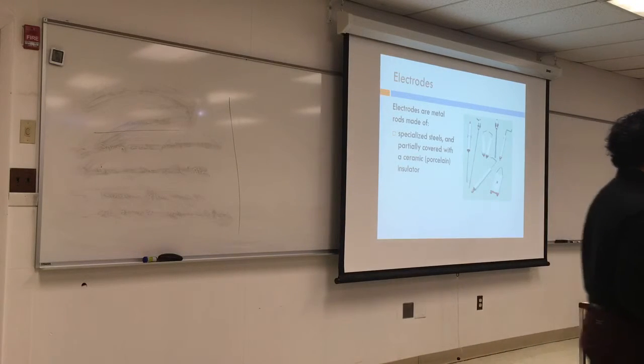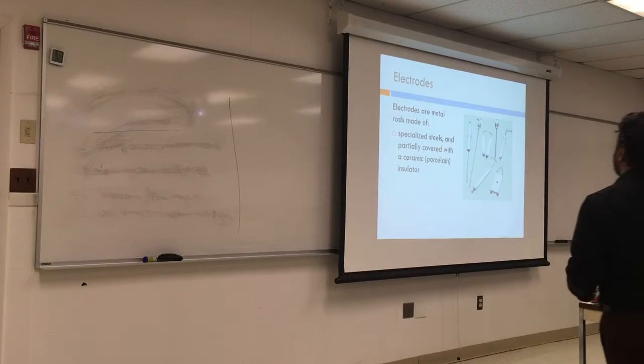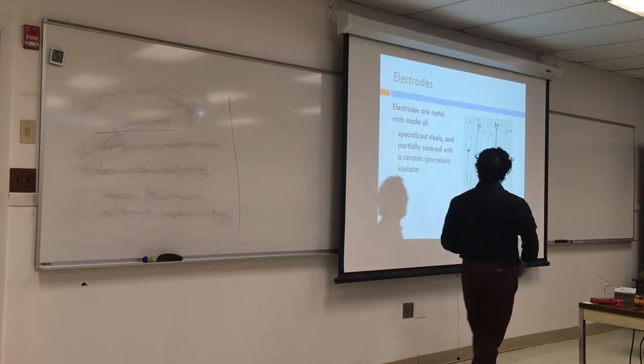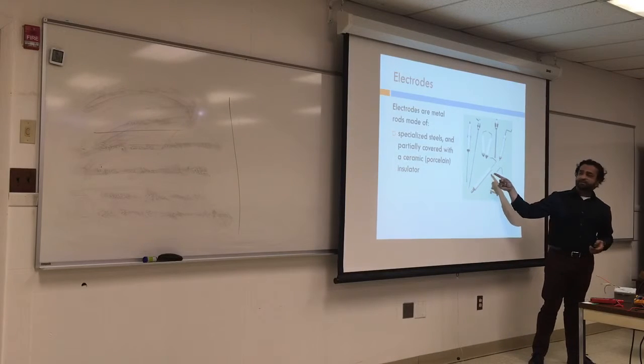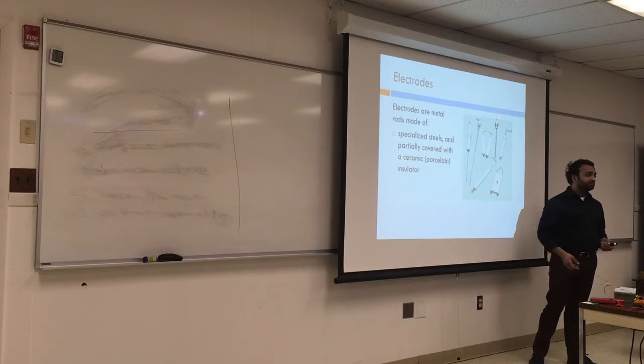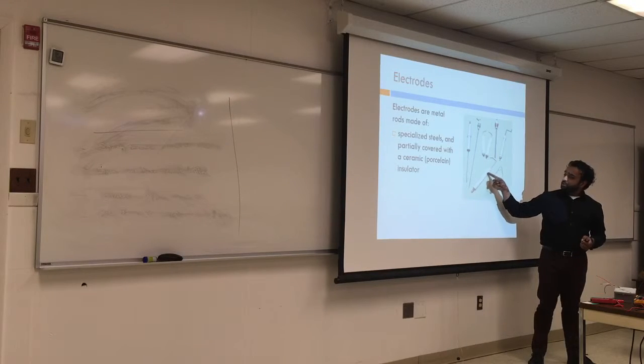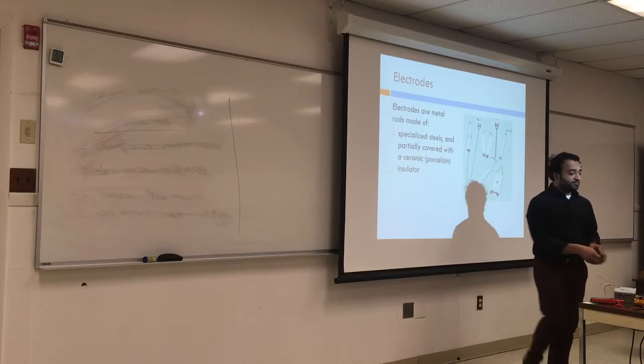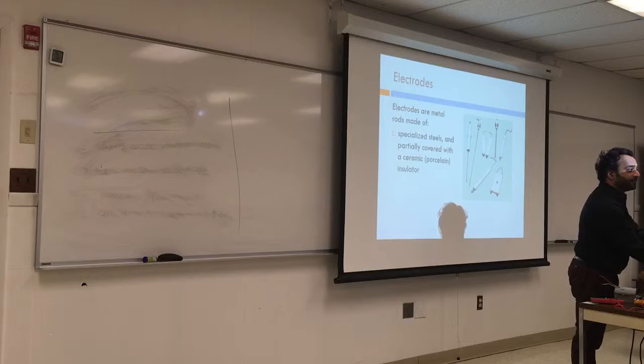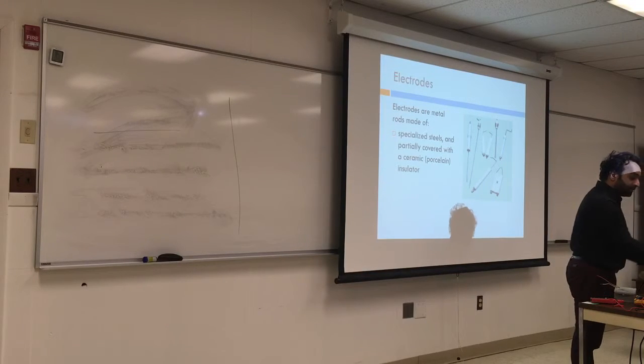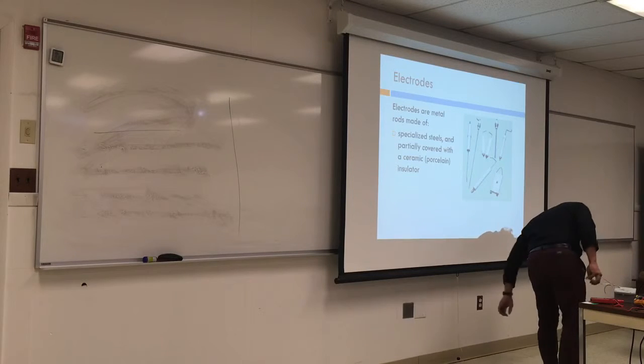These are the electrodes. Electrodes are made out of steel, and there's a lot of covering made out of porcelain or ceramics. If it's cracked, you gotta change it because again, they're supposed to insulate the voltage from coming into the casing. Because if you look here, this is all metallic. If you're touching any of that with electrodes, probably it will leak some voltage to the outside. So be careful that it's not touching anything else. And if we, again, look at the electrodes from the inside, yeah, we can have one over here.